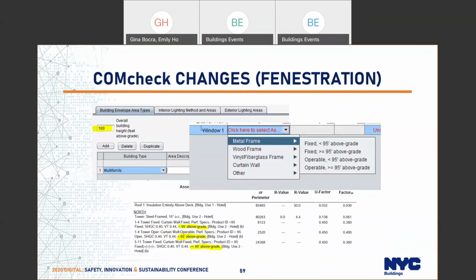All right, for fenestration, we were getting some questions in the chat box today about how to input the fenestration requirements into ComCheck, now that we have different U factors for below 95 feet and above 95 feet. One additional requirement you'll have to do is input the overall building height in feet above grade. So that's a new requirement. That's the total building height. So input that, and that will affect both the fenestration, and it also will provide the correct air barrier testing requirement. So we have requirements that are different for below 75 feet and above 75 feet. So that's what this new value does in ComCheck.